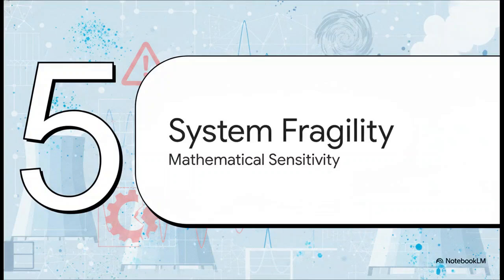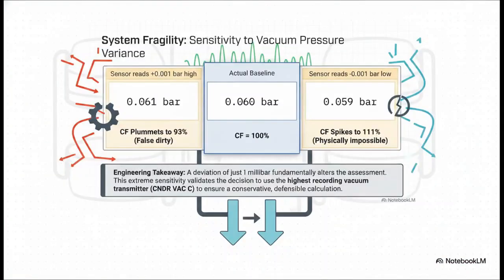So we've celebrated a perfect cleanliness score. But before we wrap up, we really need to pivot to our final section and talk about a serious operational warning: system fragility. I want you to see just how delicate these calculations actually are. Check out this sensitivity chart for vacuum pressure. Our actual baseline was 0.060 bar, giving us our 100% clean factor. But what if our vacuum sensor is out of calibration by just one single millibar? If it reads 0.061 bar, literally just 0.001 high, our cleanliness factor plummets to 93%. That triggers a totally false dirty flag and could lead to millions in unnecessary maintenance. Conversely, if it reads just 1 millibar low, the math spikes to 111%, which is a physical impossibility.